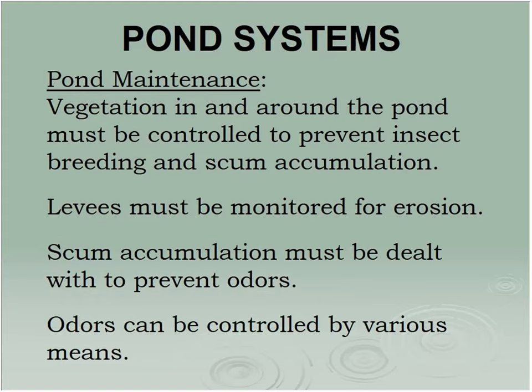But they do take some maintenance. Here we got stuff called duckweed that generates around the edges and all that, promotes insect growth, that's to be dealt with. The levees, we got a bunch of muskrats and that sort of stuff. If you're not careful, the banks will give way and then all of your water goes down into the stream, which is not very desirable. And since they are very low tech and not much control, they can be kind of smelly, but since they're out in the middle of nowhere, doesn't seem to be much of an issue for anybody.